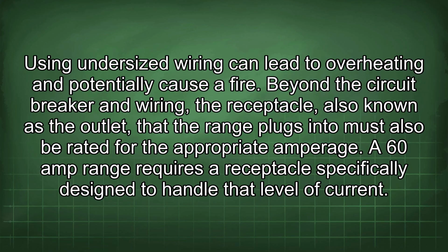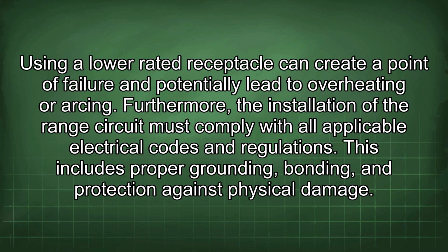Beyond the circuit breaker and wiring, the receptacle, also known as the outlet, that the range plugs into must also be rated for the appropriate amperage. A 60 amp range requires a receptacle specifically designed to handle that level of current. Using a lower rated receptacle can create a point of failure and potentially lead to overheating or arcing.